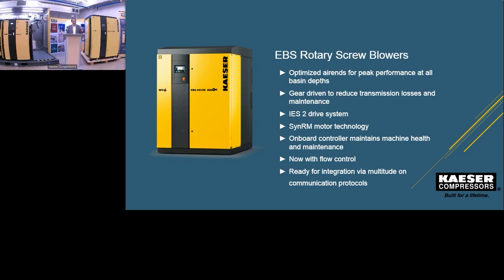And lastly, this machine can operate locally. It has a nice controller on it. It has e-stop button, start, stop. You can do all these things. You can put your DO signal in there and have it regulate if you so want from locally. But it also has a variety of communication protocols which can be integrated, different languages, which can be used to integrate into your plant PLC or SCADA. So everything that's on that controller, you can extract out. And of course, you can tell it to start, stop, as well as what speed or regulation that you're looking for. So that is all I wanted to point out here on this new machine. It's our EBS screw blower, and hopefully we can find a few more homes for these out there.